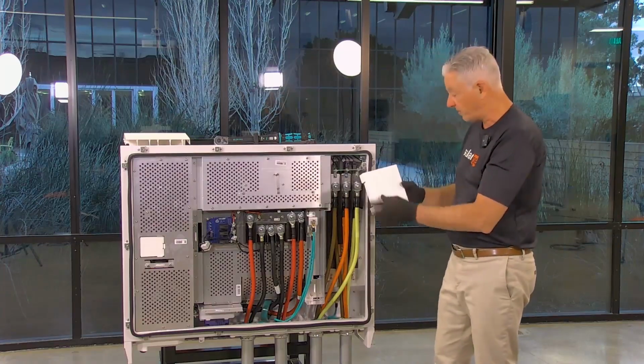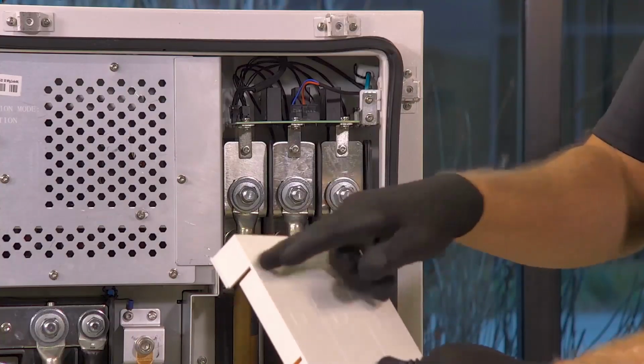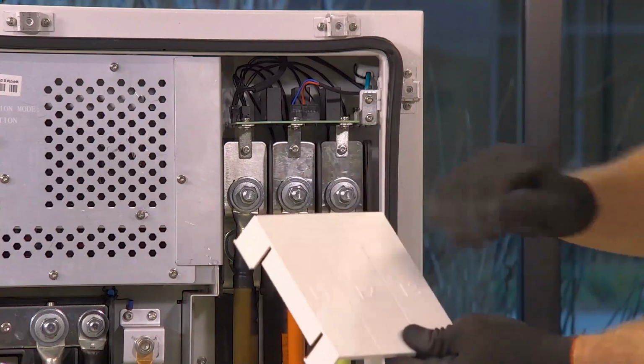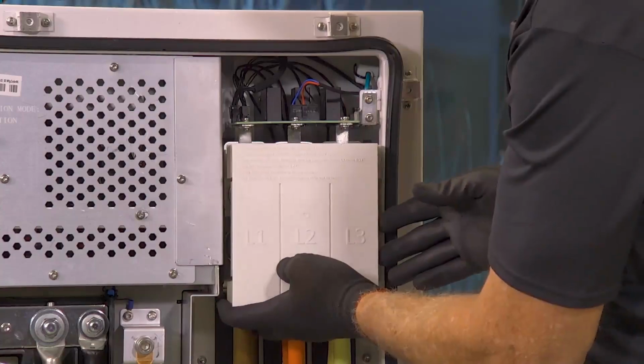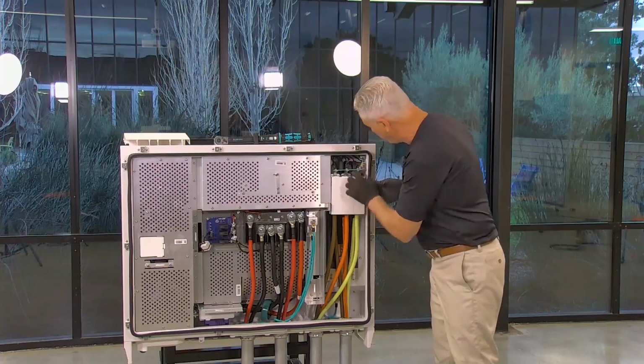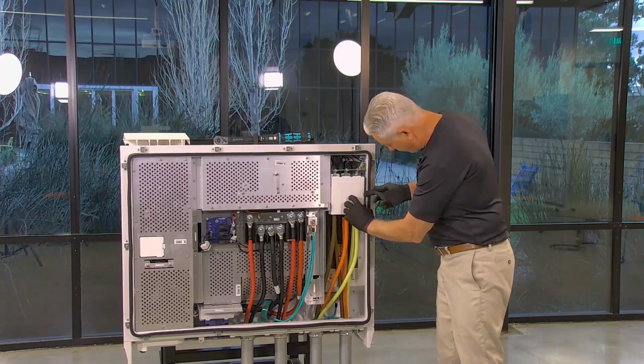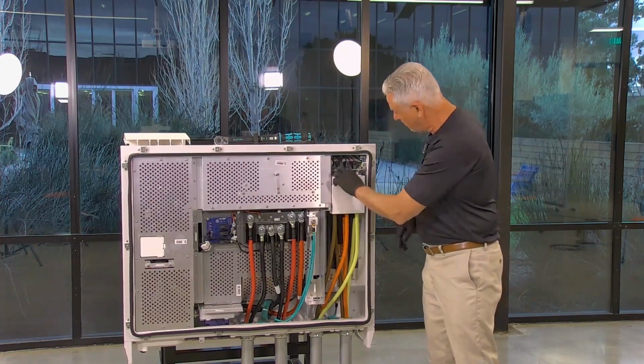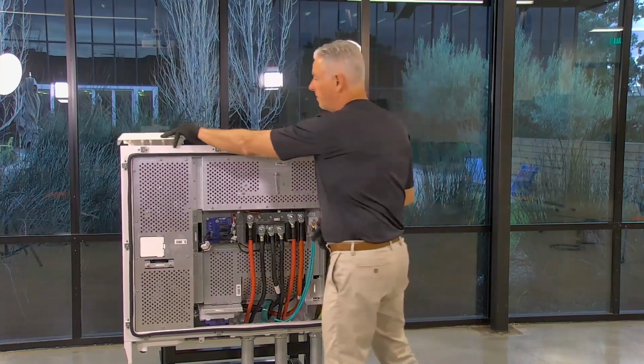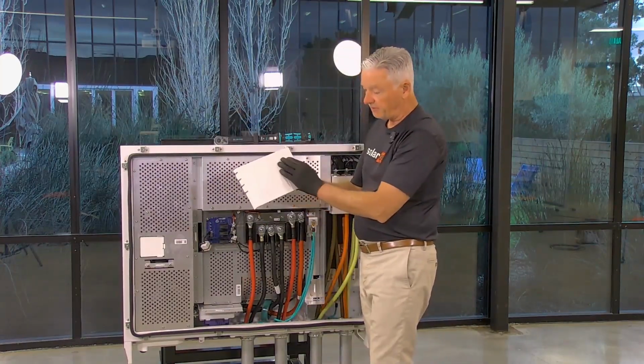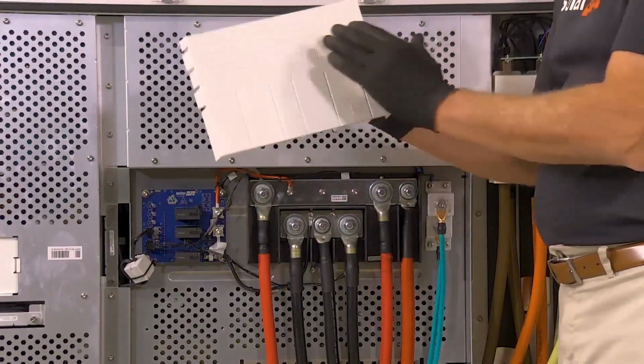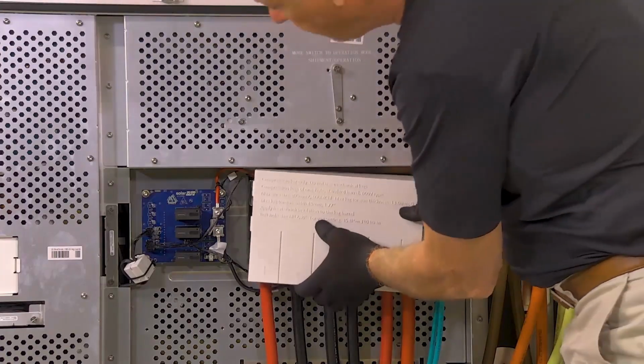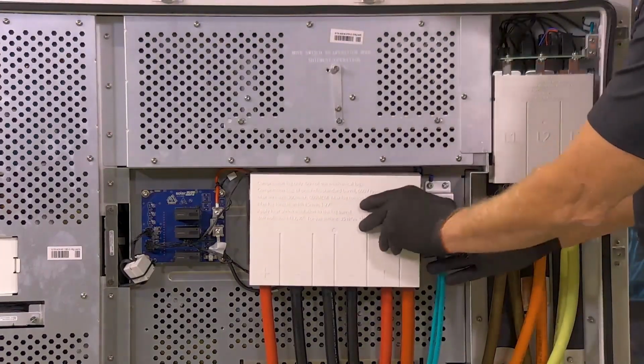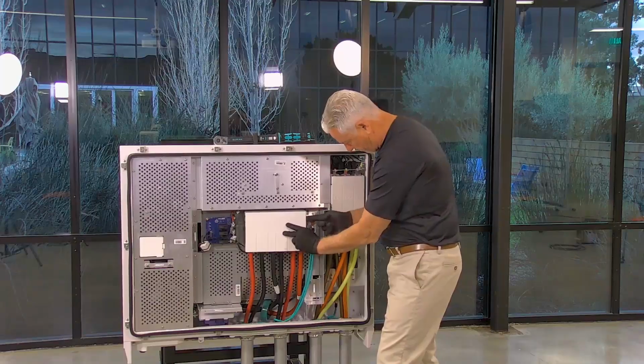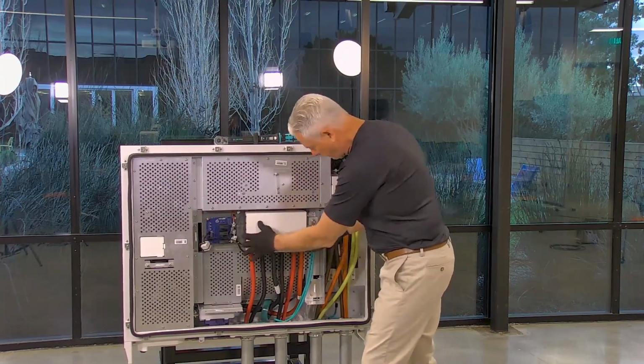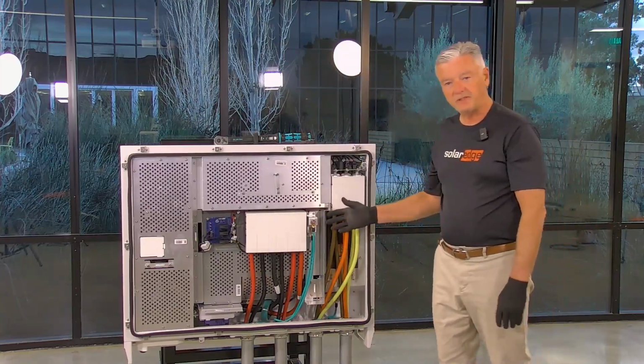By the way, all the specifications for your compression lugs, for your conductors, and for the torque values are found on this cover. Same thing on the DC side. All of the specs for the compression lugs, the conductors, and all of your torque values are here. Now that's all there is to making the electrical connections. Now we can put the lid back on.